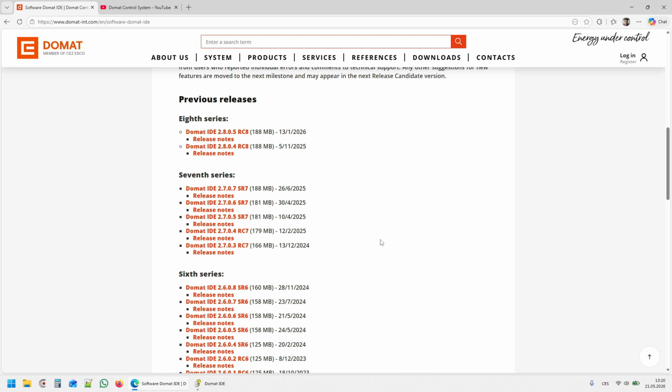Runtime is backward compatible, so if I have a new PLC with a newer runtime version, but the project is in an older version of the program, it is not a problem, and I can upload the program as I please. If it were the other way around, an older PLC with an older runtime version and a program in a newer version of the IDE, the IDE will first prompt me to upload the newer version of the runtime to the PLC. After that, it is possible to work without restrictions. Uploading the runtime takes only about 1 minute.